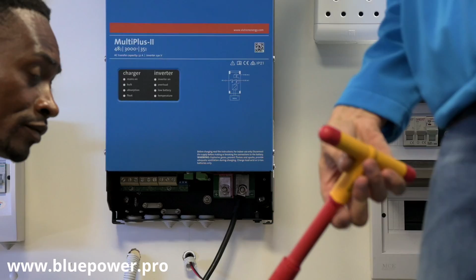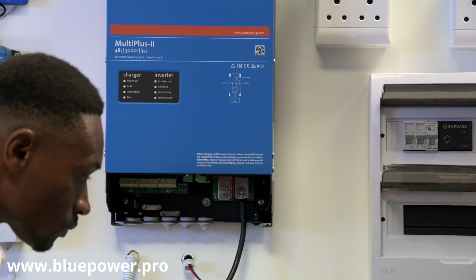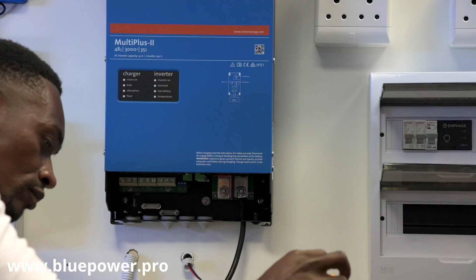The torque ratings for the inverter connections are indicated in the manual, so do take note that you don't over tighten them. For demonstration I'm just tightening it loosely since I'm not drawing much power. Recommended torque rating - I'm not 100% sure, I think it's 5 Newton meters, but that's for an M8 bolt. Just tighten it until it stops, then turn it back half a turn.